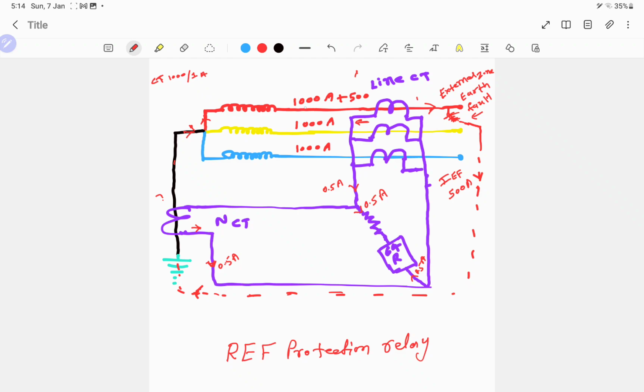So the current here at the R phase will be 1000 amp normal current plus fault current 500 amps. It will be a total of 1500 amps flowing through the primary winding. The CT ratio here is 1000 by 1 amps. So here it will flow 1.5 amp from the secondary of the R phase CT, and the rest of the windings are balanced like 1000 amps. So line CT2 and line CT3 will have a balanced load, I mean 1 amp.